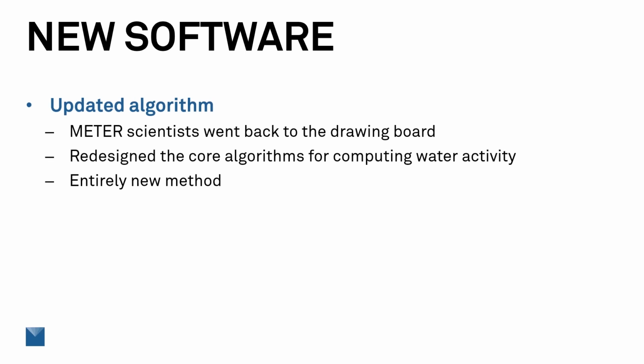Great. And now that we've covered the hardware, let's move on to the software. For this device, is water activity being calculated the same way, or is the TDL2 using some type of new method? Yeah, so this is the most exciting part really about the new TDL, is that by incorporating that new processor, our scientists were able to go back to the drawing board and really take a look at how we had calculated water activity from those optical absorbance values. So the new TDL uses an entirely new method for computing the water activity from the absorbance peak. Now, what that allows for is just a more consistent, more robust measurement. So our clients will see improved performance on a day-to-day basis with the new and improved TDL.